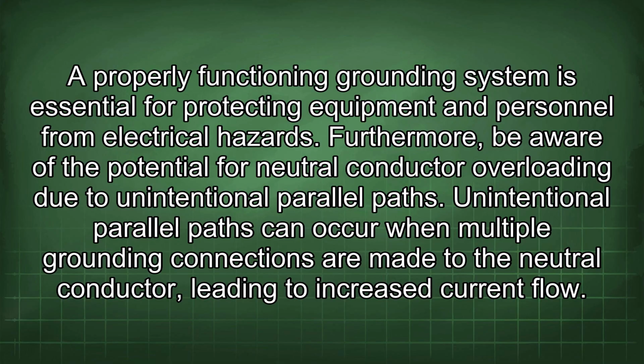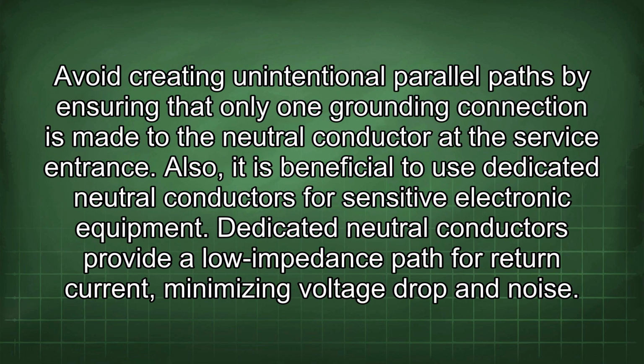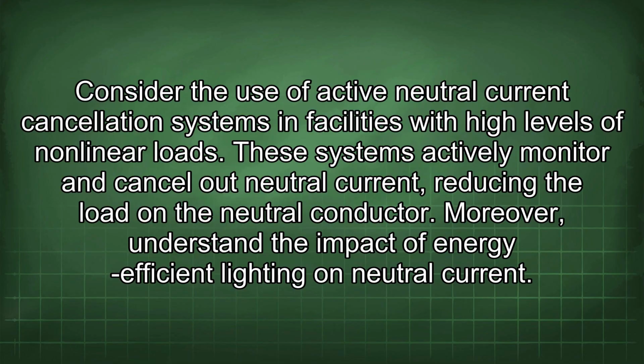Furthermore, be aware of the potential for neutral conductor overloading due to unintentional parallel paths. Unintentional parallel paths can occur when multiple grounding connections are made to the neutral conductor, leading to increased current flow. Avoid creating unintentional parallel paths by ensuring that only one grounding connection is made to the neutral conductor at the service entrance. Also, it is beneficial to use dedicated neutral conductors for sensitive electronic equipment. Dedicated neutral conductors provide a lower impedance path for return current, minimizing voltage drop and noise. Consider the use of active neutral current cancellation systems in facilities with high levels of nonlinear loads. These systems actively monitor and cancel out neutral current, reducing the load on the neutral conductor.